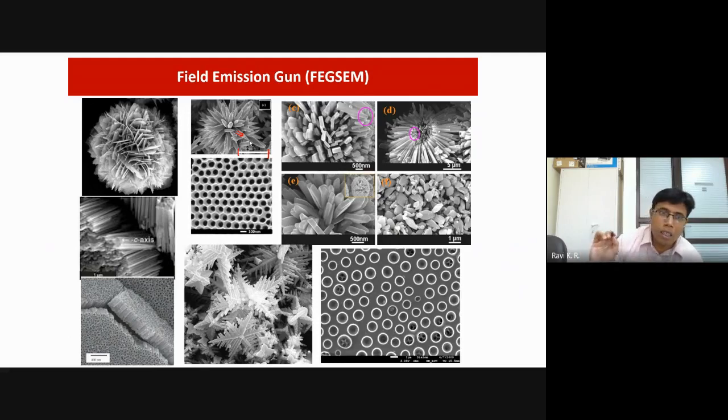So we don't actually get it in a conventional microscope. You can go up to 4 to 5 micrometer feature size, and then you can get reasonably good resolution. But again, it depends on the machine and on the operator. It depends on your sample preparation also. That is very important. One part, though I may not discuss in this particular class: if you look at this image, it is very poor. If you look at these regions, I can see there is charging.